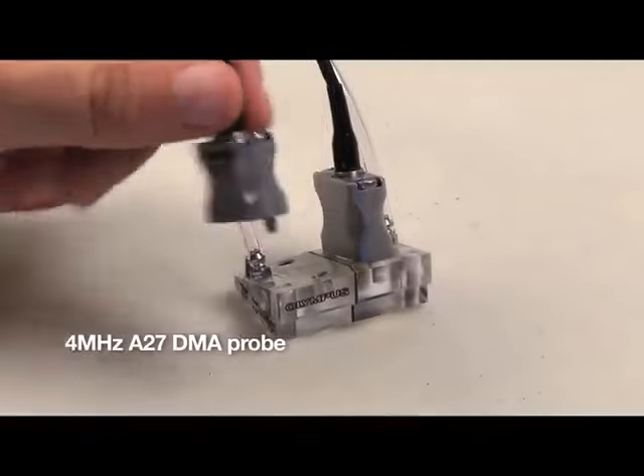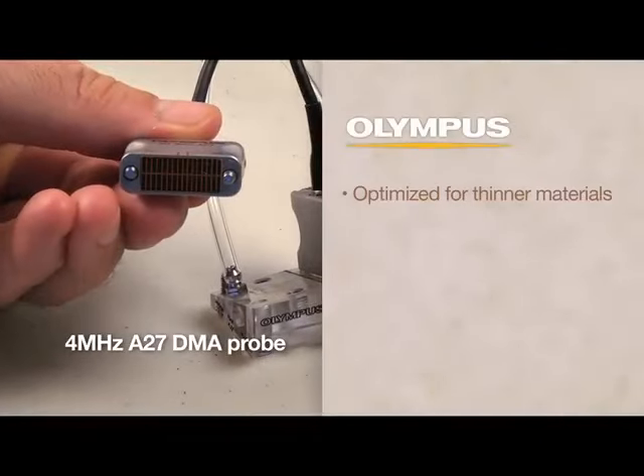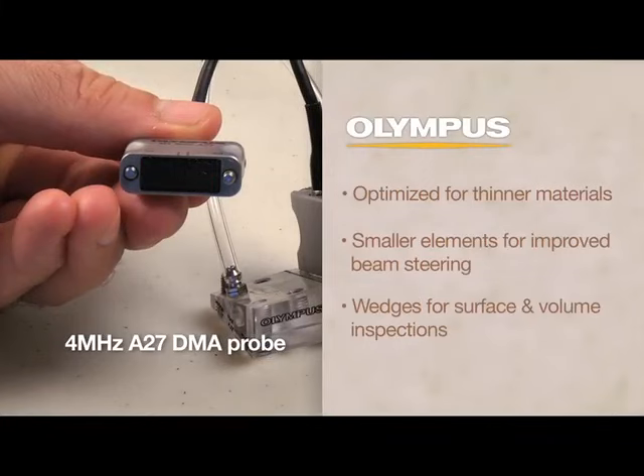The 4 MHz A27 DMA probe uses a 2x16 element configuration in each housing and is optimized for thinner materials using smaller elements for improved beam steering and surface inspections.